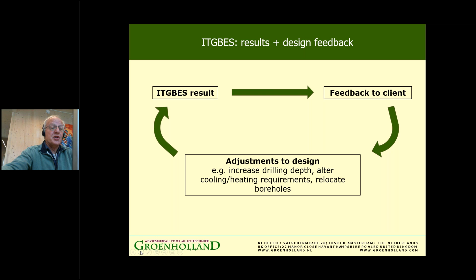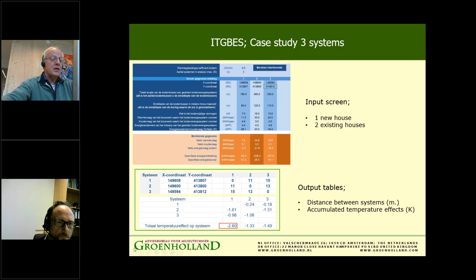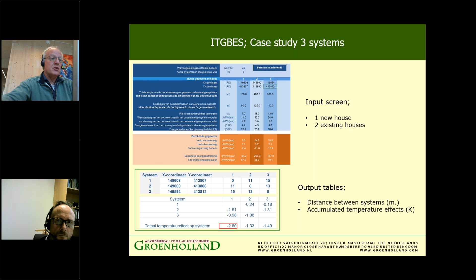And this is what I'll show as an example on just 3 houses, because that's simpler to show. What you have here is 1 new house and 2 existing houses. Again, we have the data input into the model, into the program, and the output in the extraction rates, etc. And from the output tables on the bottom end, you can see the distance table with the X and Y coordinates. Yeah, so the houses are a bit closer together. And you can see the new house, number 1, has a temperature effect caused on this house of minus 2.6. So this house is 1.1 degree below the legal threshold, the maximum allowable threshold. So this is what you now get from this simple example. Now, if we go to the next page.